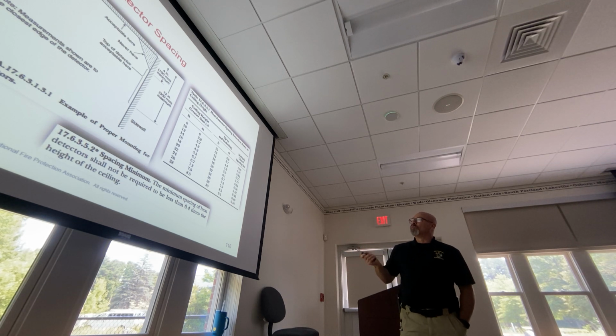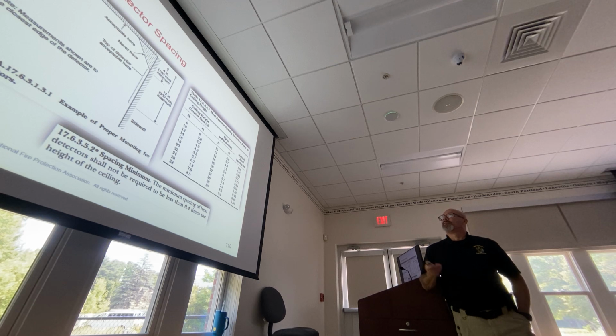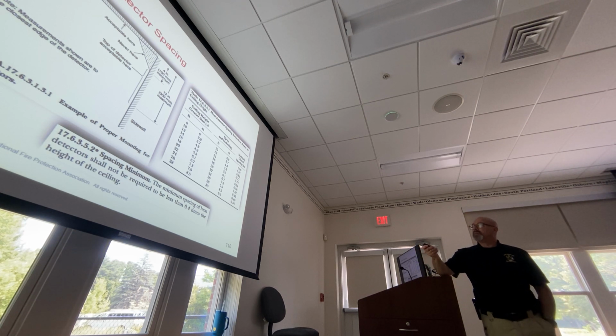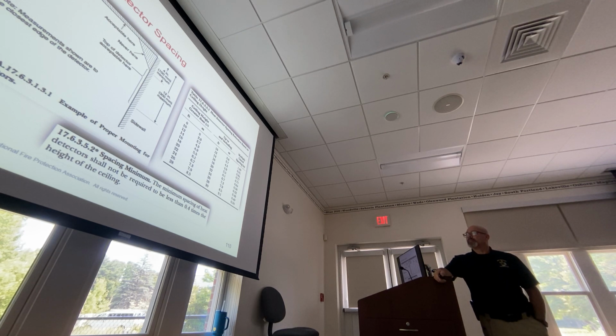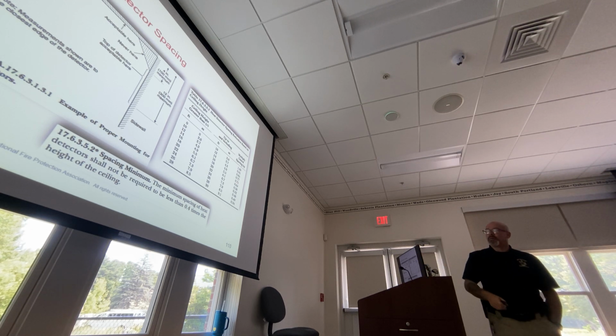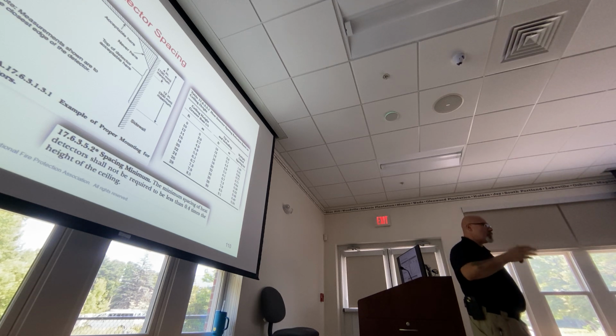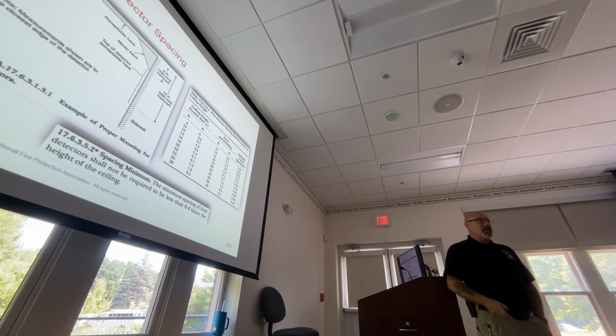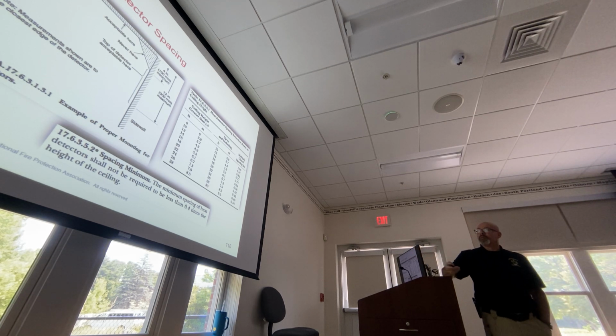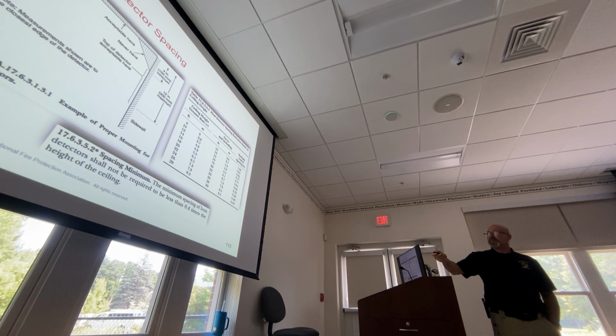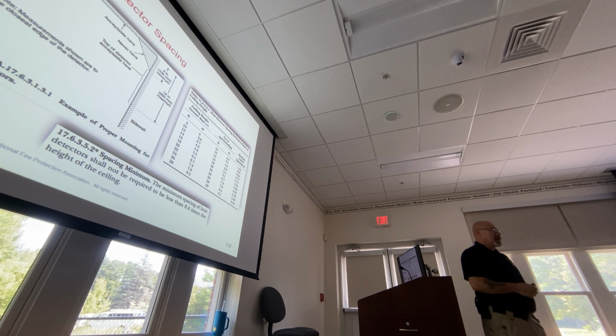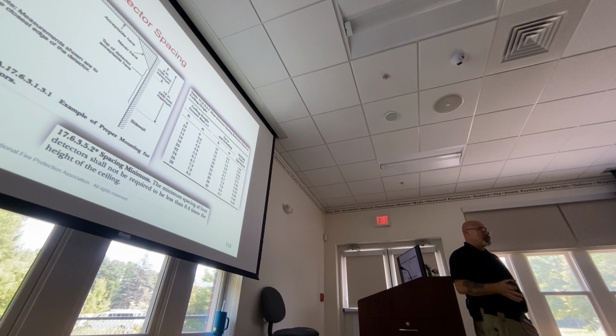This table is what you will probably see for a question. Or it'll ask, what's the heat detector spacing reduction based on the ceiling height? If they tell you that you have a ceiling 17 feet, your ceiling height greater than 16 but less than or up to and including 18, so 17 falls within that range, you multiply by 0.71. That's all you need to know. You don't need to do the math. You don't need to know any further than that, okay? You just have to know how to read the table. If it's 17 feet, that falls between 16 and 18, 0.71 is your multiplier. That's all you need to know with this table, okay?